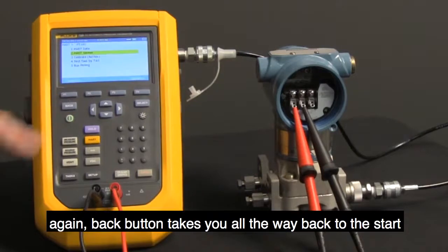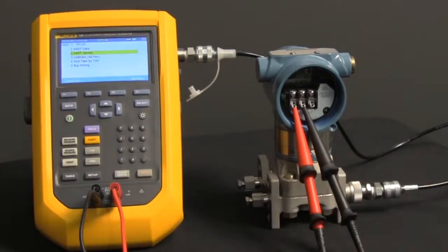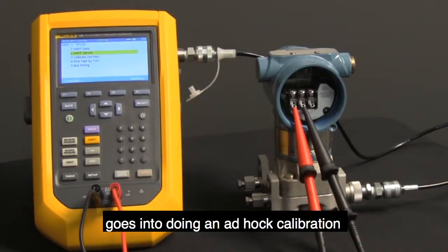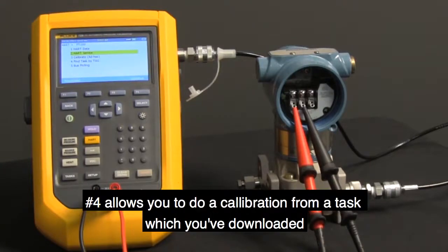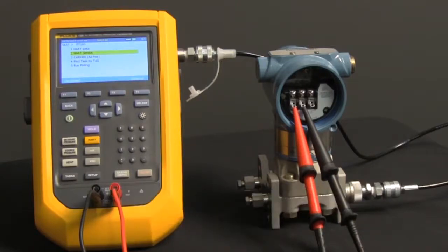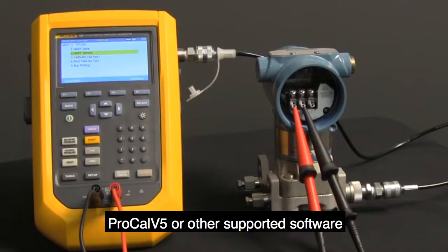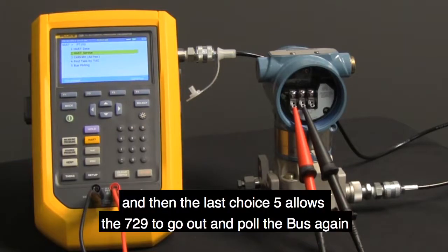Again, back button takes you right back to the start. Choice number three goes into doing an ad hoc calibration. Number four allows you to do a calibration from a task which you've downloaded from DPC track to ProCal V5 or another supported software. And then the last choice, five, allows the 729 to go out and poll the bus again.